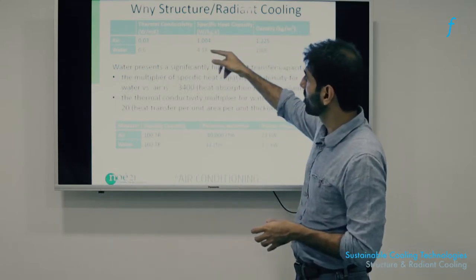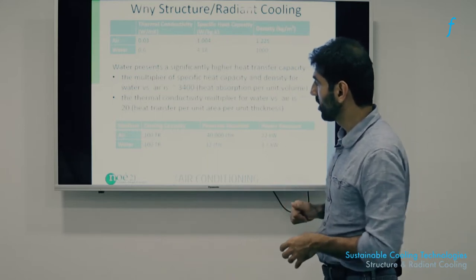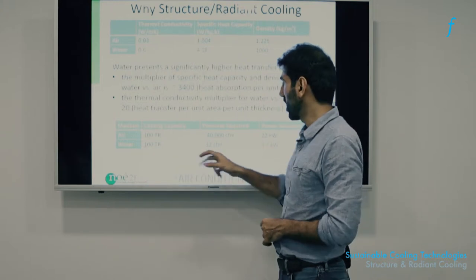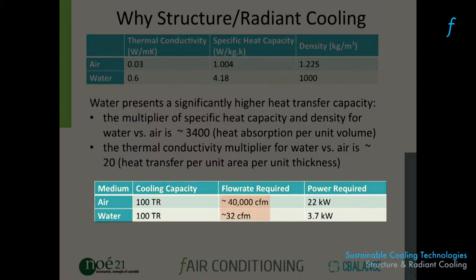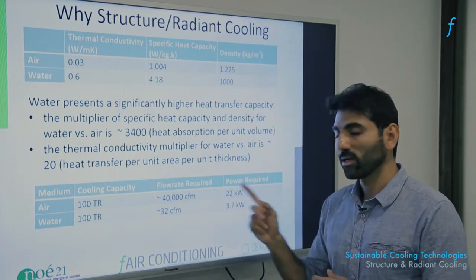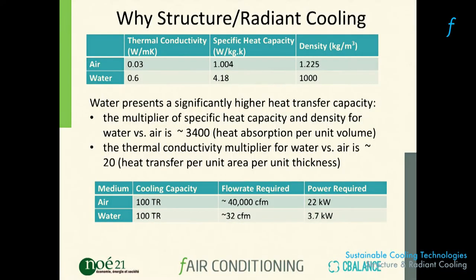The implications of switching the cooling medium from air to water are significant. To create 100 tons of cooling with an air-based system, you would need to pump approximately 40,000 cubic feet of air per minute. To create the same amount of cooling with water as the medium, you need only 32 cubic feet of water per minute. Pumping a compressible fluid like air versus an incompressible fluid like water results in a massive power reduction when choosing water.